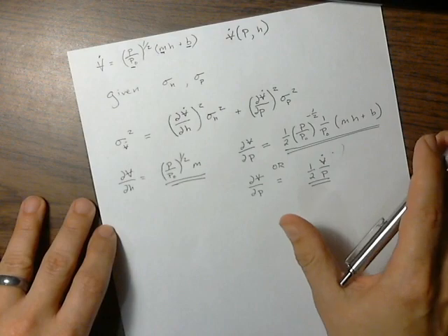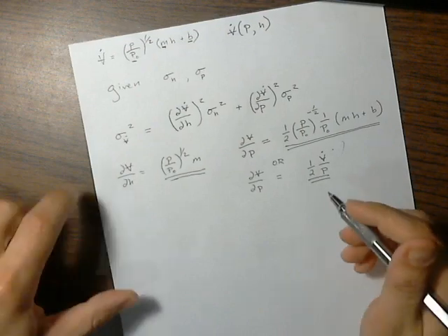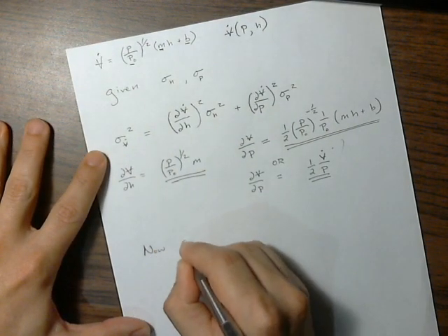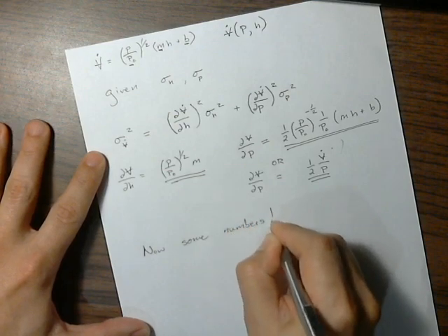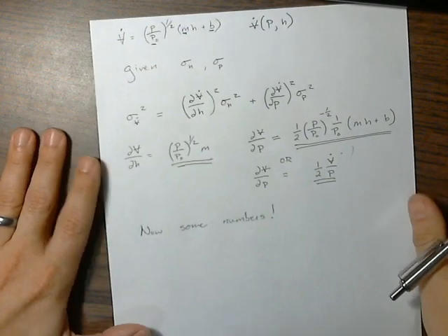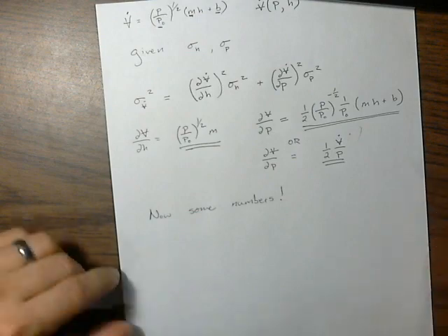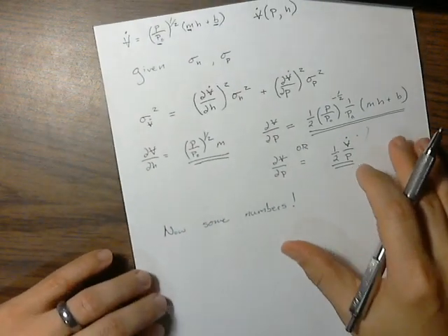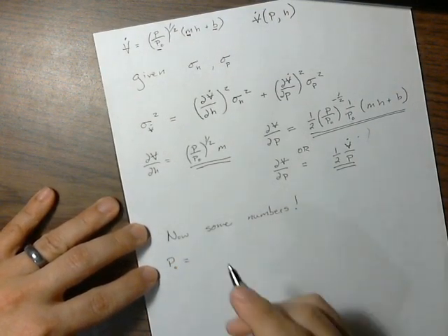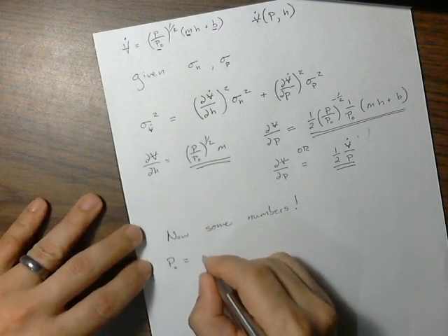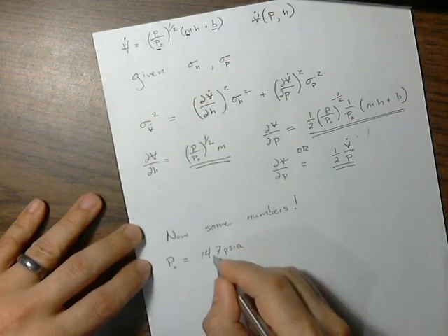Okay, so we've got that much. Now let's add some numbers. So let's go ahead and give this calibration some numbers. Normally I like to poll the class for numbers, to prove that I haven't prepared the answer in advance and we're really generating it on the fly. I'll just have to make them up myself. So for P0, let's assume we're operating at atmospheric conditions for the calibration. Let's work in PSI, why not? At atmospheric pressure, we're at 14.7 psi-A, so that's 14.7 psi absolute.